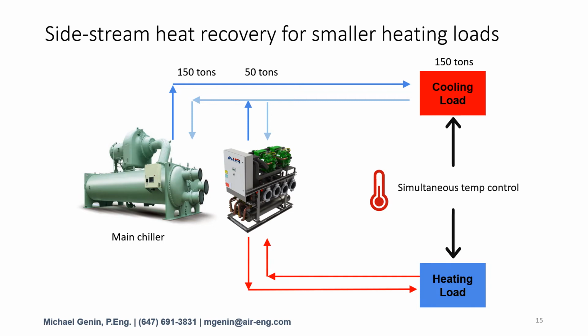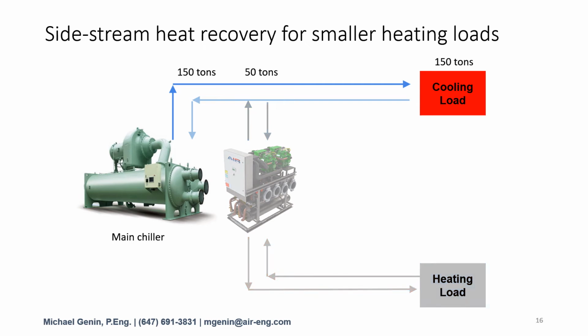One thing to note is if the heating load would disappear, the heat recovery chiller is unable to operate. It has no way to reject its heat without a heating load. The cooling load in this case must be completely handled by the main chiller. Hence, we have a total cooling load of 150 tons, yet we have a total installed chiller capacity of 200 tons. This is something to consider when you calculate the ROI. In most instances, it won't matter if the main chiller is an existing machine.